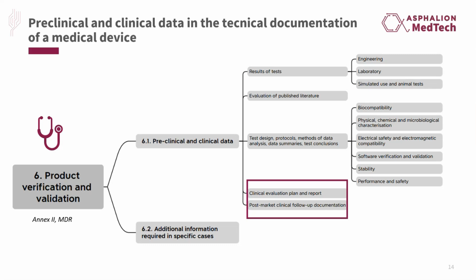However, a specific type of preclinical data, that is performance and safety testing with animals, will not be directly considered in the clinical evaluation of the medical device, but it has a very important role. So the preclinical data goes into the technical documentation that will be assessed during the conformity assessment of the medical device by a notified body.